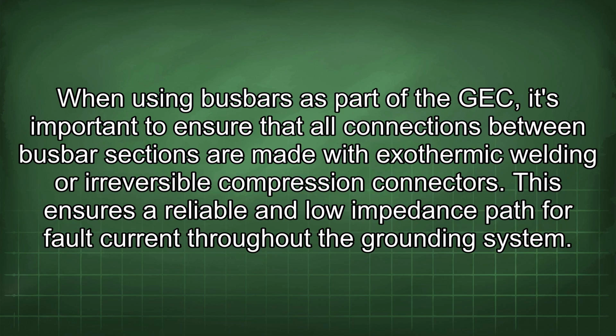conductors. When using busbars as part of the GEC, it's important to ensure that all connections between busbar sections are made with exothermic welding or irreversible compression connectors. This ensures a reliable and lower impedance path for fault current throughout the grounding system.